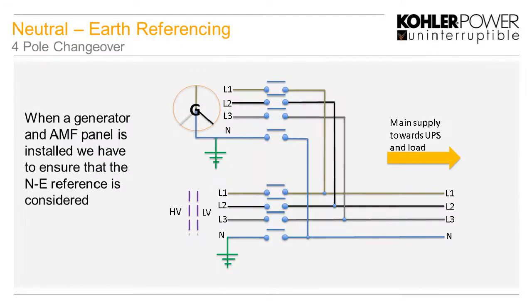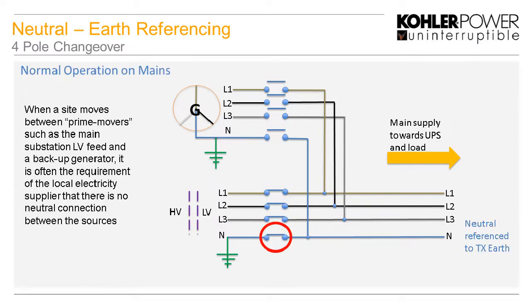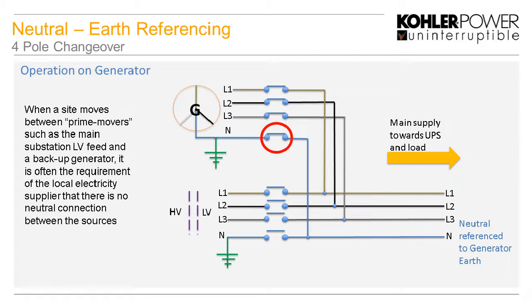So if we look at this little diagram here, we can see this 4-pole changeover. And typically when we're on mains, you can see here that the output neutral is referenced to the earth at the star point of the transformer. Okay, so during the changeover period, there is no connection to any star point while both circuit breakers are open. So when we go back onto the generator, now the output neutral is referenced to earth.